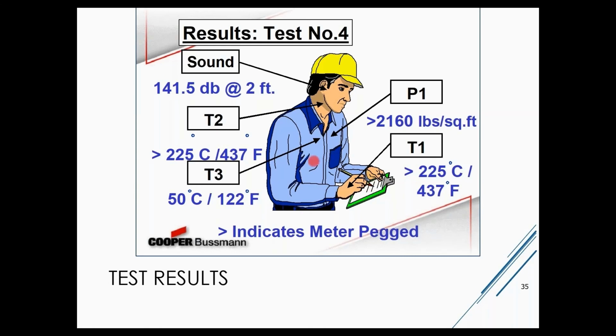But here's the other important thing I like to point out. The mannequins had arc-rated garments on, and when we discuss them in a longer day, we'll talk about ATPV ratings and E sub BT, which is the break open threshold. It's where the garment actually broke open. ATPV is heat flux; it's heat transfer from one side of the garment to the other side of the garment. So the heat on the outside versus the heat on the inside.